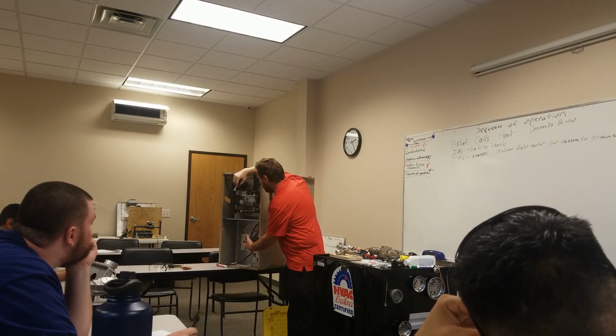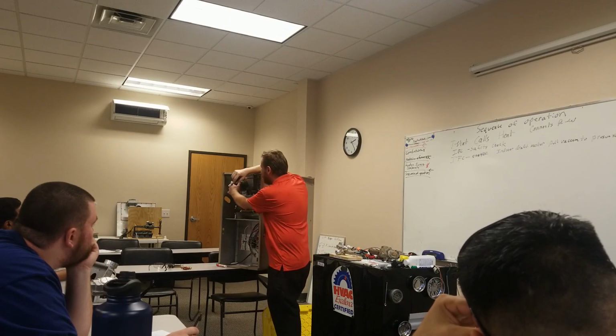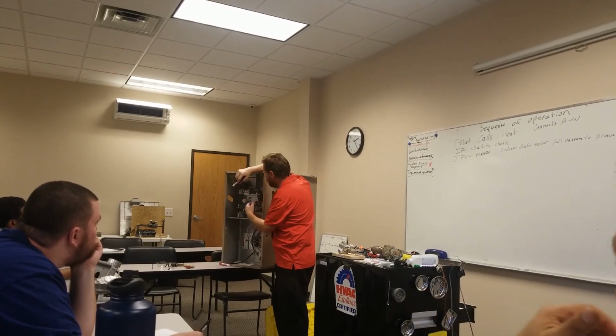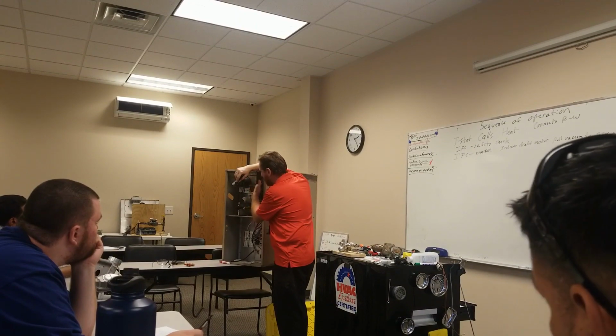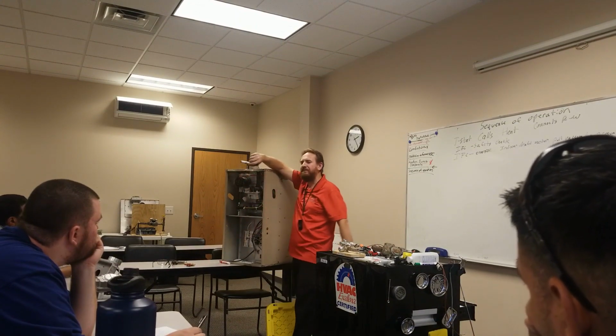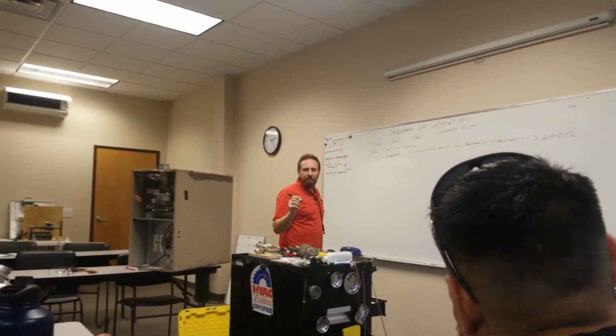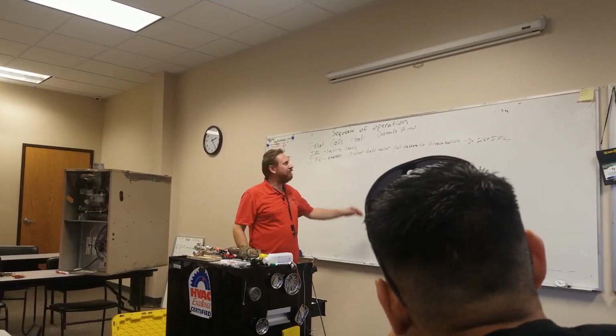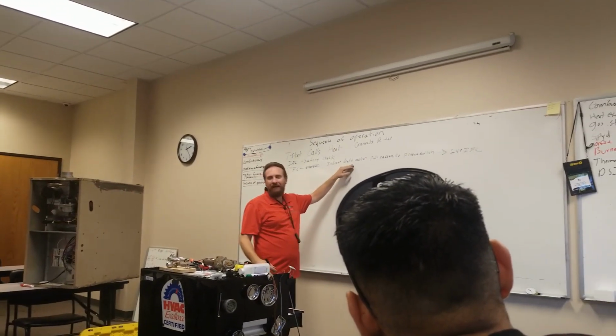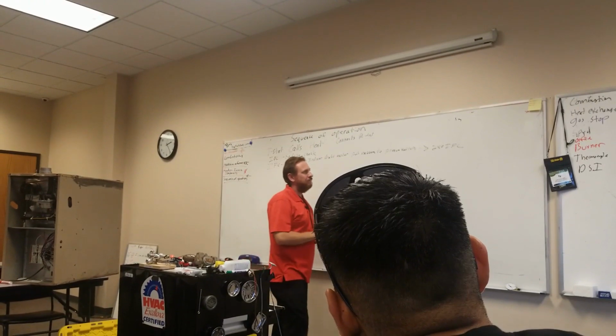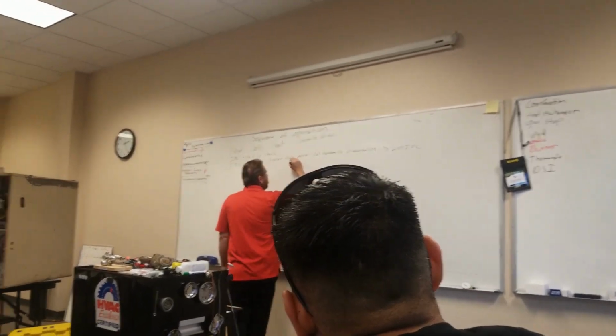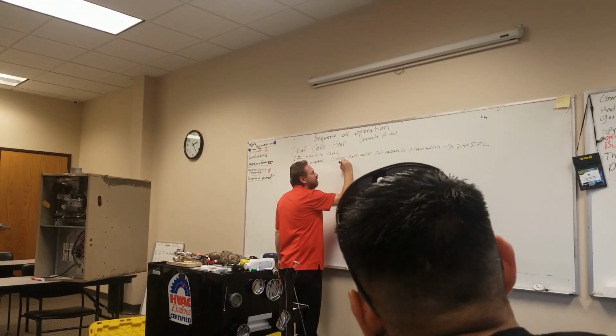So it's going to do a safety check. It's going to energize this motor. This motor is going to pull a draft through the heat exchanger, and also to the pressure switch. The pressure switch is going to tell the IFC that it's still working. Before the IFC does anything, though, it's going to leave this motor running for a pre-purge.